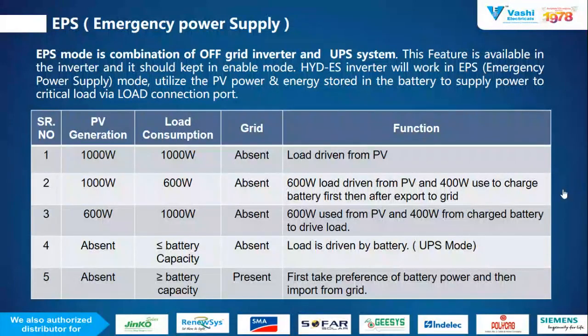Second condition, when the PV generation is 1000 watt and load consumption is 600 watt, your load consumption has decreased. This load consumption continuously changes through the whole day, and it is sensed by the CT connection, which gives feedback to the hybrid inverter. Wherever there is load fluctuation, the CT senses the load current and gives feedback to the hybrid inverter. According to that, the inverter works, right? So in this second condition, when PV generation is 1000 watt, load consumption is 600 watt and the grid is absent, 600 watt of load is driven from PV and 400 watt is used to charge the battery first, and then surplus power is exported to the grid.